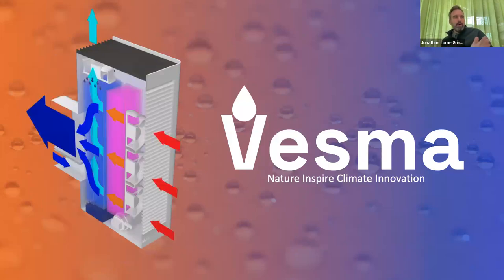So what we're going to end up doing on the pink side is first dehumidify that air using dry screen. So we're going to have a less humid air that is then introduced to our indirect evaporative cooler, which is going to mean that the evaporative cooler performs better, but it also means we're going to bring in less humidity. And that also means ultimately that, as much as we showed that dry screen works well in Miami, and we tested our evaporative cooling system in Boston, it's going to fundamentally mean that indirect evaporative cooling with dry screen can be applied in any climate.